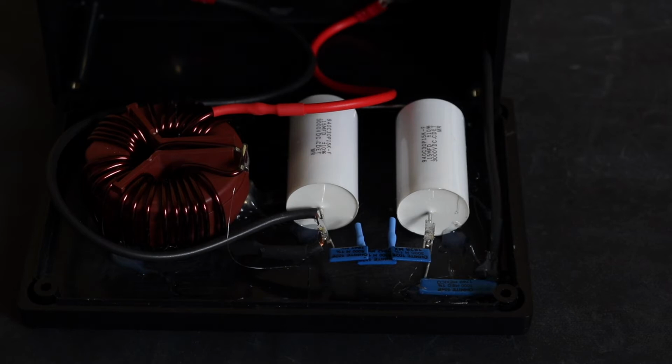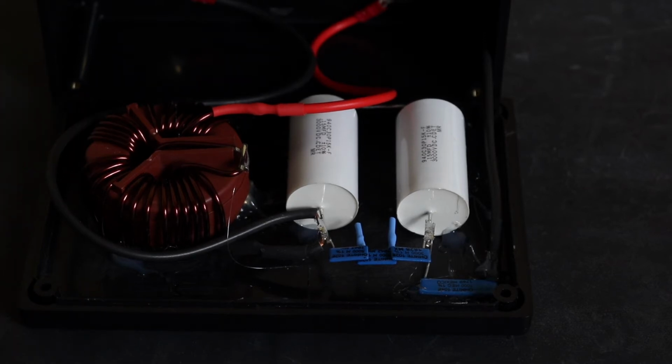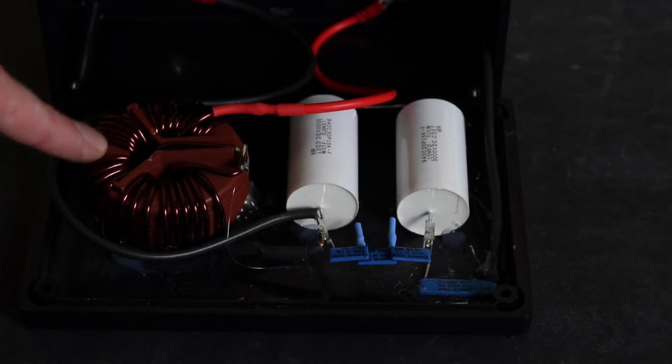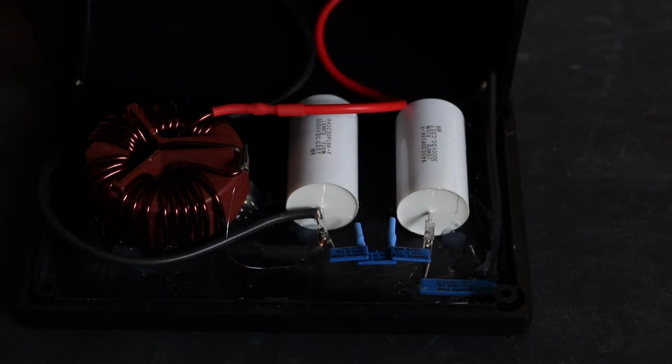For the ductors that I use, that will just give me a DC winding resistance to measure. But these are quite beefy, so the micro ohm meters kick out about 10 amps, and this will obviously take that, no problems. So I'll assemble the unit up, and then I will demo a micro ohm meter test, and I'll demo a polarization index test on it as well. This particular unit can actually take up to 5,000 volts, so I'll test that with a different tester than the MTR 105 that can put out the higher voltage levels.